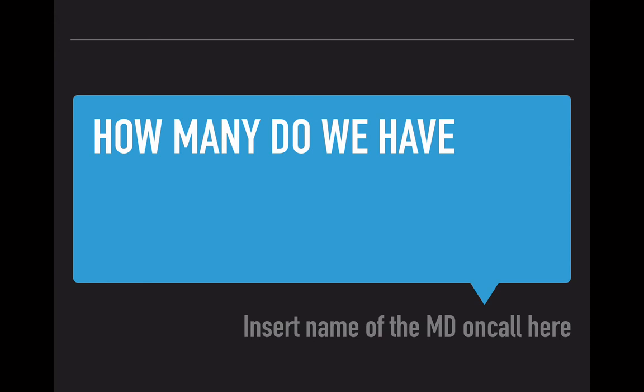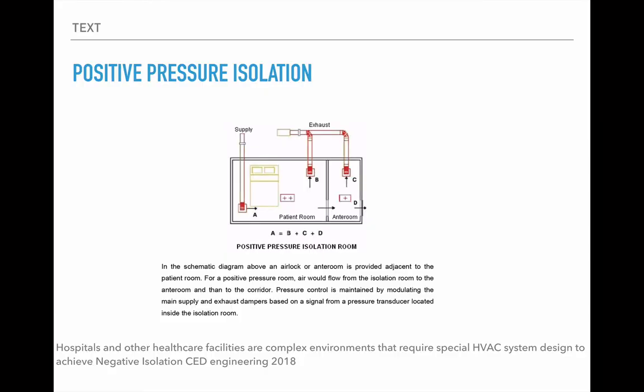A little bit about what negative pressure isolation means. This is what positive pressure isolation looks like. The whole trick between negative and positive pressure is D on this diagram, the door to the rest of the hospital. In positive pressure isolation rooms, you want to push air out so no contaminated air gets into the patient's vicinity. The idea is to keep the room clean so the patient doesn't get infected. The air inlet has to overcome the exhaust system and ambient airflow. There's a way to calculate that, I'll get to it in a sec. A should equal B, C, and D here, so the inflow equals the outflow, keeping air always pushed out of the patient's way.